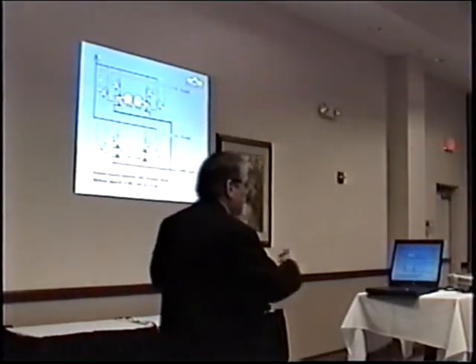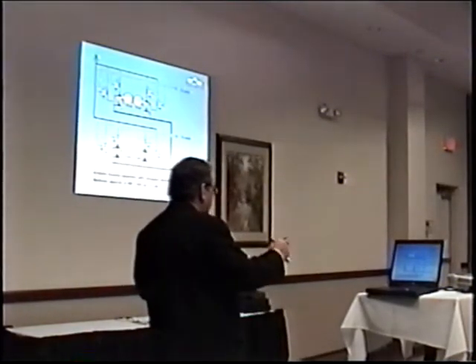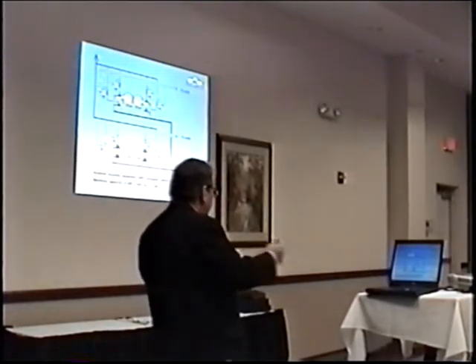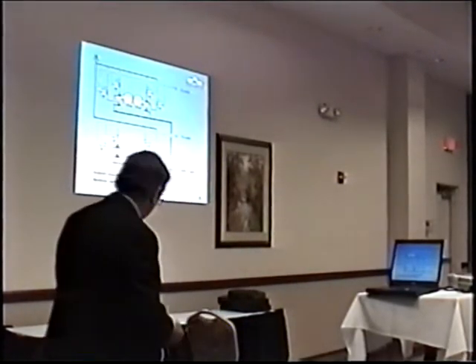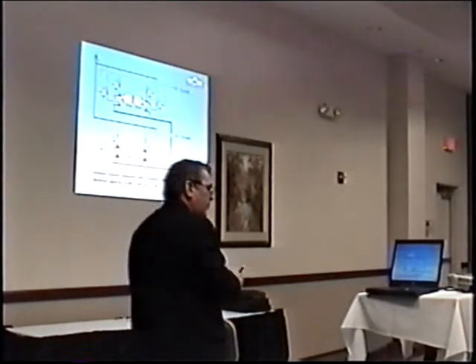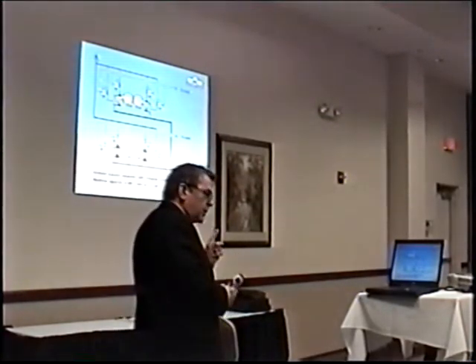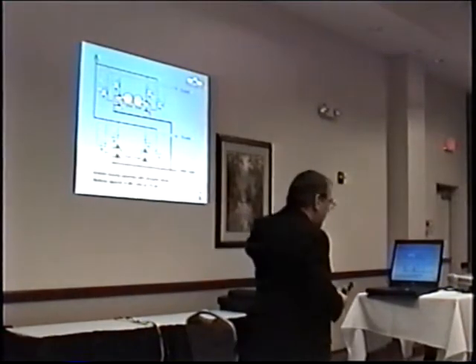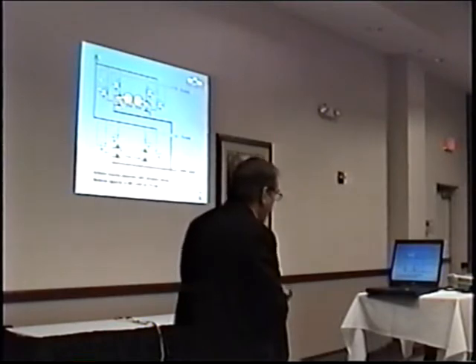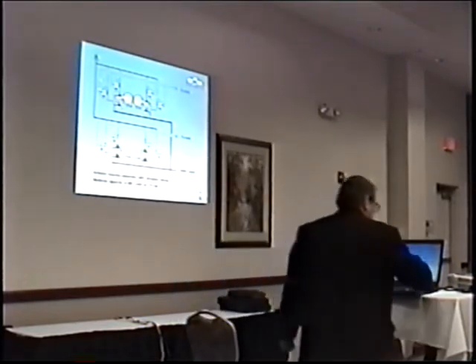So you've got many small pumps, small unloaders. The system will glide up with the demand and adjust itself to a variable demand rather nicely. You can use one huge pump and one huge unloader valve, but then you're trying to supply one little tiny sprinkler with a great big pump, and you've got an unloader or pressure relief valve fluttering away, giving very inefficient performance.